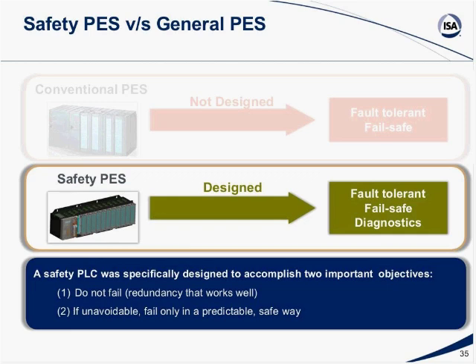So we obviously cannot use a conventional PLC to perform safety functions, mainly because of the lack of fault tolerance and fail-safe capabilities. A logic solver or safety PLC is specifically designed to accomplish two important objectives. The first one is it should not fail, and it should have redundancy that works well. But if failure cannot be avoided, it must fail only in a predictable, safe way.